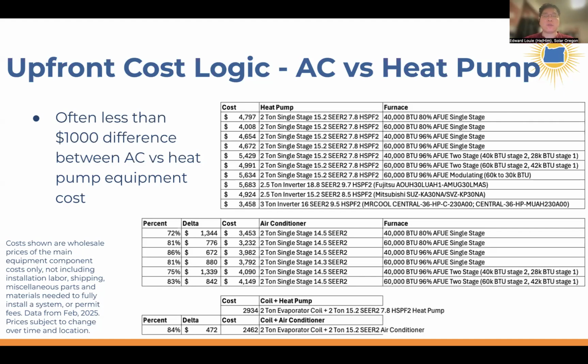So the parts list to go with an air conditioner and a furnace system is not much different than a system that has a heat pump with a furnace. The difference between an air conditioner and a heat pump is, for the most part, a reversing valve, and that reversing valve in the outdoor unit costs maybe $20 or $30 at the factory. So very small amount of additional cost. And then at the wholesale equipment cost, you're often talking about less than $1000 in difference between getting a straight air conditioner versus a heat pump.